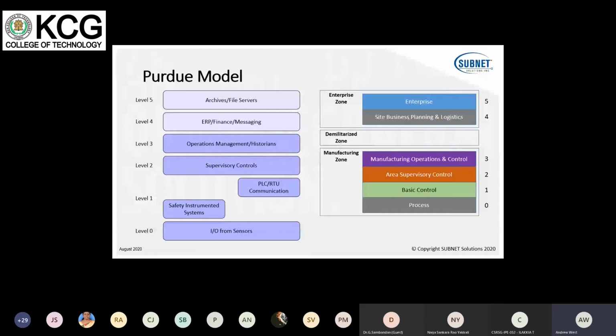Typically, we also separate safety functions, and in the power industry, think of protection as being the safety function, equivalent to an oil refinery emergency shutdown system. So the safety zone is often separated from the manufacturing zone, even though they may physically be in the same place. And within the manufacturing zone, we might have subzones of things that get grouped together.